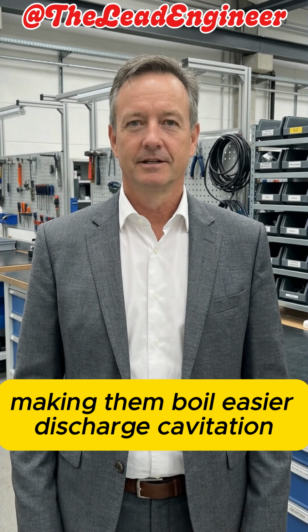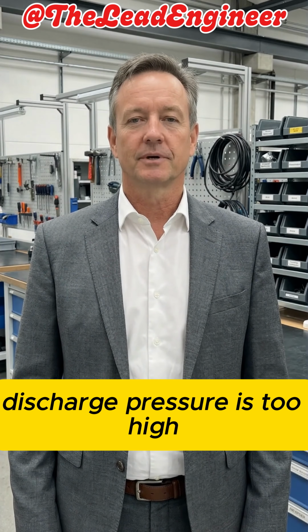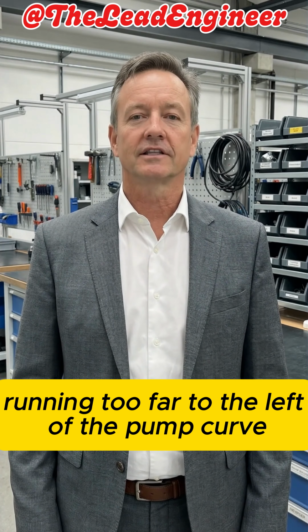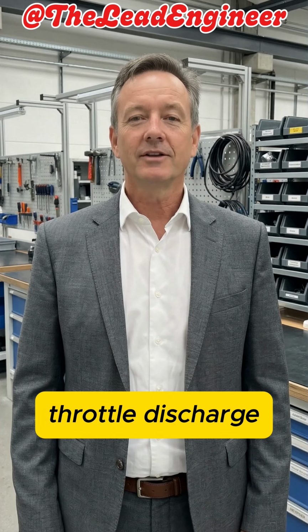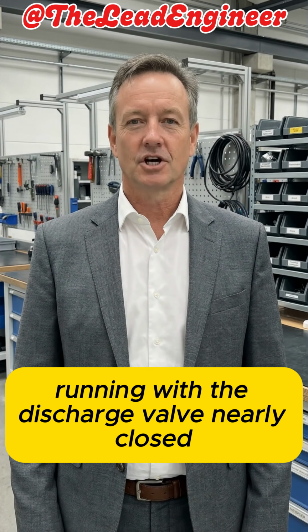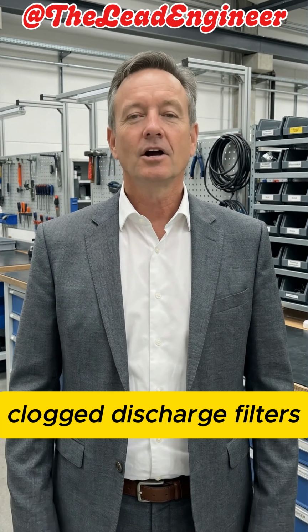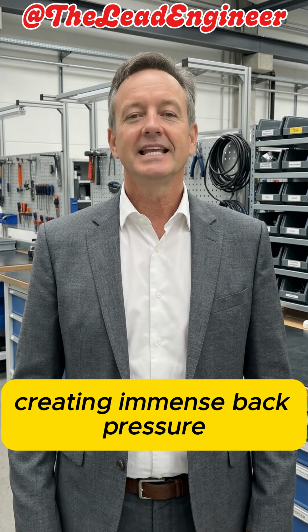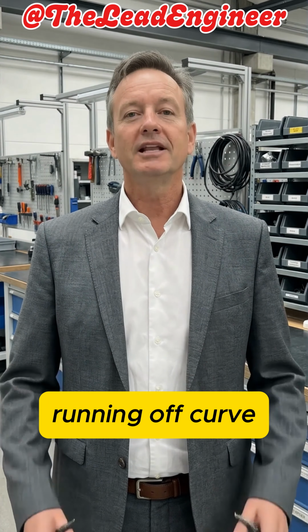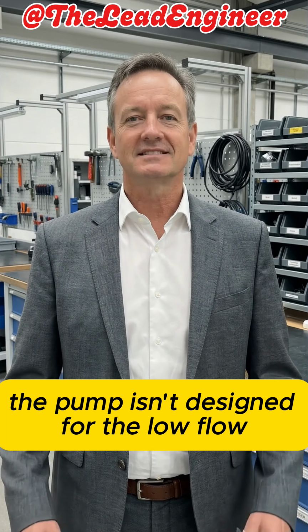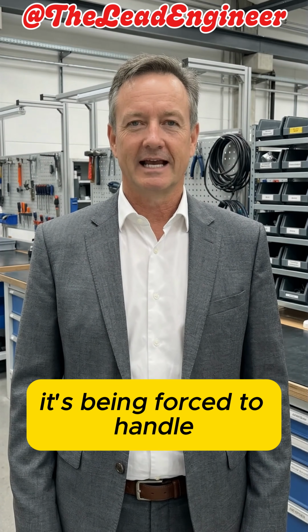Discharge cavitation. This occurs when the pump discharge pressure is too high, running too far to the left of the pump curve. Throttle discharge. Running with the discharge valve nearly closed. Clogged discharge filters, creating immense back pressure. Running off curve. The pump isn't designed for the low flow it's being forced to handle.